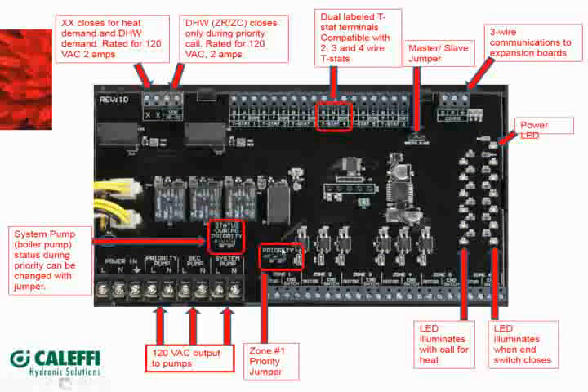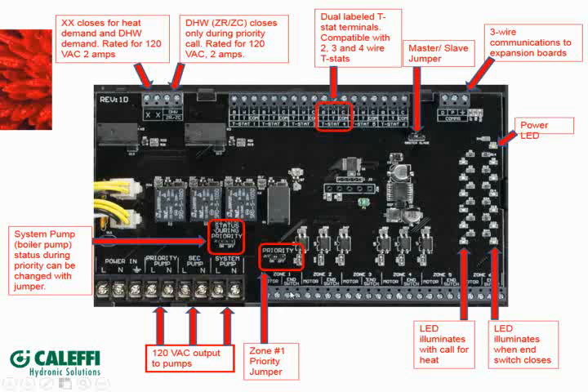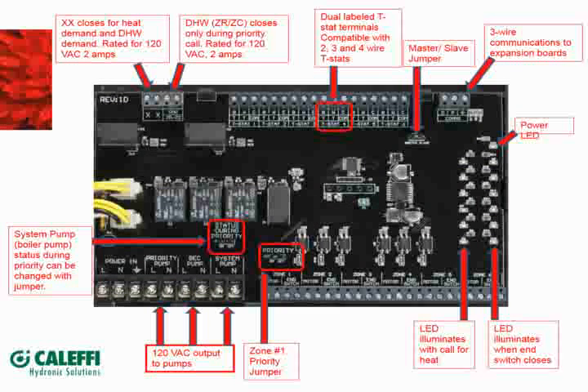We need a jumper in the end switch if you're using a pump, because when the thermostat or the aquastat calls, this contact has to be made before it knows it should fire, because it doesn't know if you're using a valve output here or you're using a pump here. So a jumper in there will cause the unit to fire as soon as the aquastat calls. But it'll fire your priority pump, and then depending upon where you have this jumper, the system pump, if it's on, if this jumper's on, the system pump will fire as well. If it's off, the system pump won't fire. I'll show you some slides on that, why you'd want to do it that way.